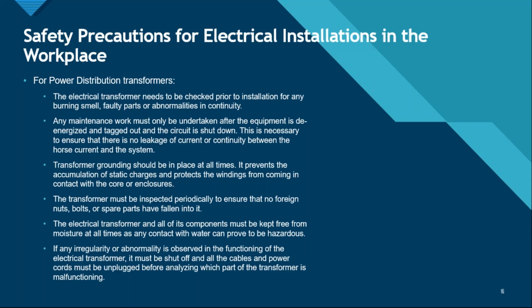Transformer grounding should be in place at all times. Whenever there is testing and maintenance happening of an electrical system, the transformer needs to be shut down, it needs to be locked out, it needs to be tagged out, and the isolation needs to be verified.